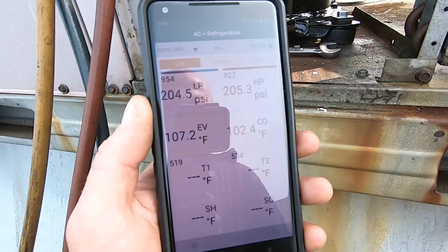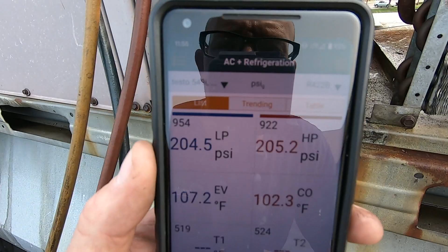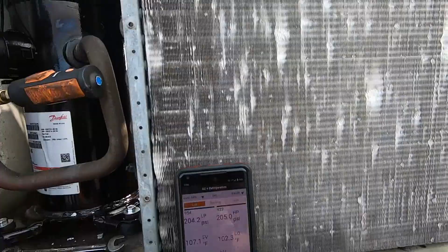Get the vacuum pump. All right everybody, I got a pressure test on it, just above 200 pounds. We're gonna let that sit for a bit. I'm gonna get the compressor wired back up, and we'll get our vacuum going. But everything went pretty well, so I'm pretty confident we're gonna be good.